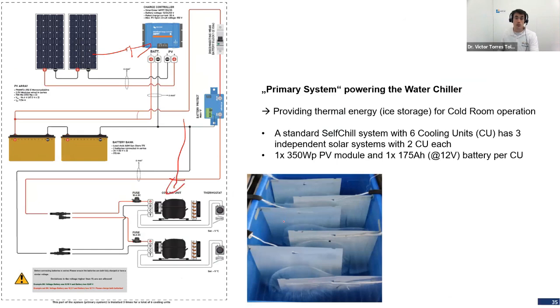And here you see what's happened inside the water chiller, right? So you have the evaporator plates of the cooling units. They produce cooling energy, and as soon as you get to 0 degrees, because they are immersed in water, they start to produce ice around the evaporator plate, right? And this is what makes you be able to have an ice storage system.